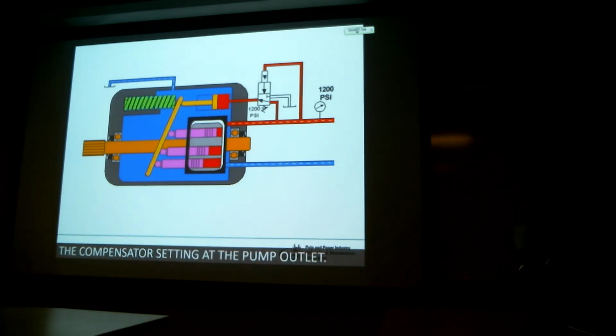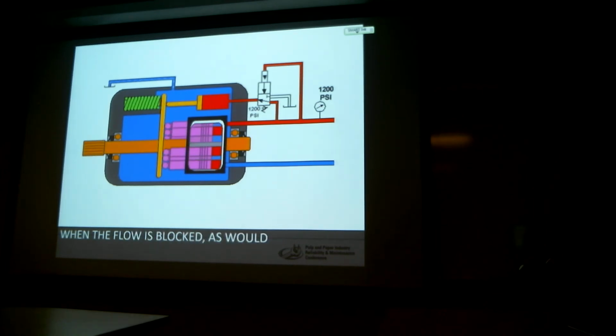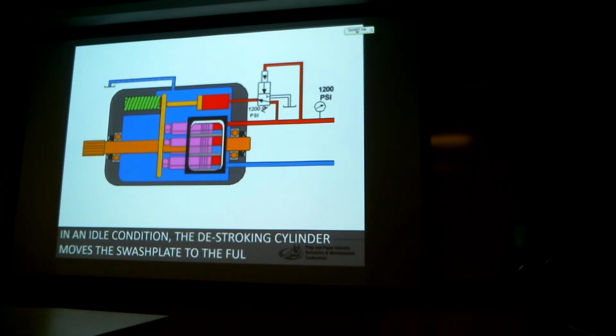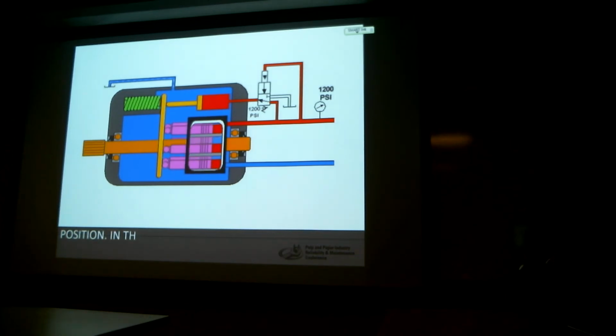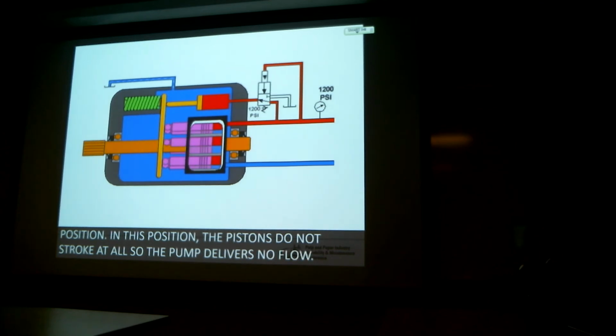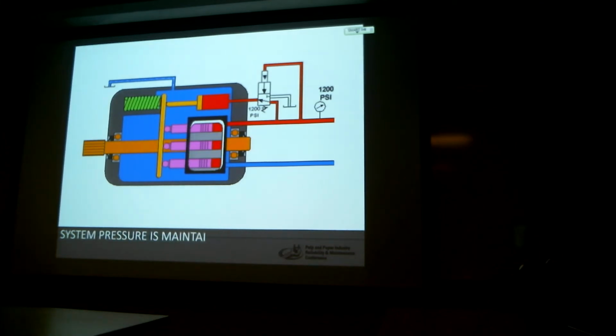When the flow is blocked, as would happen when all directional valves are closed and the system is in idle condition, the destroking cylinder moves the swash plate to the full vertical position. In this position, the pistons do not stroke at all, so the pump delivers no flow. System pressure is maintained at 1200 psi, and any drop in system pressure will cause the pump to stroke and keep the pressure up.